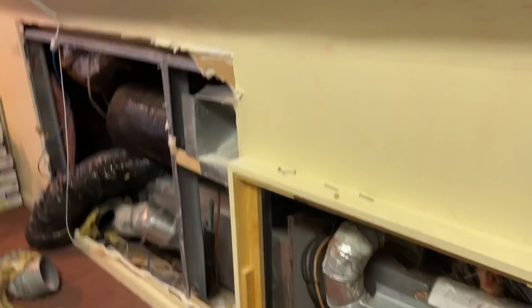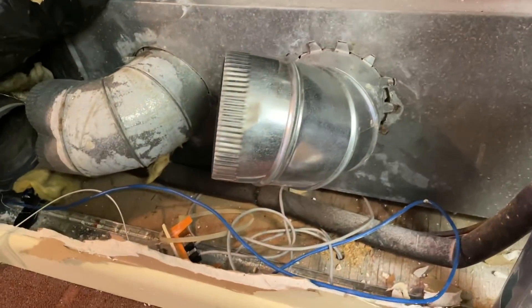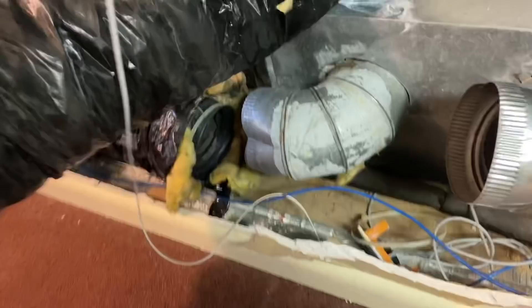We opened up the wall. Here is our supply plenum which ends right there. We have a six-inch takeoff here — look how they did that, total hack job. There wasn't enough room so they just put a piece of flue pipe in there. Here's another six-inch takeoff — it's not even a takeoff, they just took a 90 and got that in there. And another six-inch right there, again not even a takeoff, just a 90. Pretty corrosive situation.